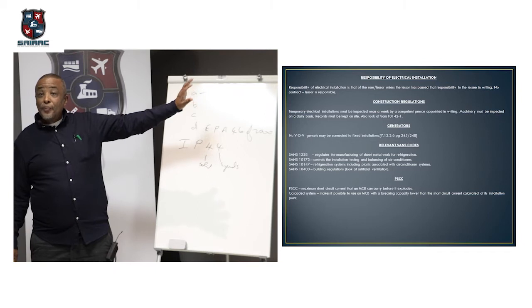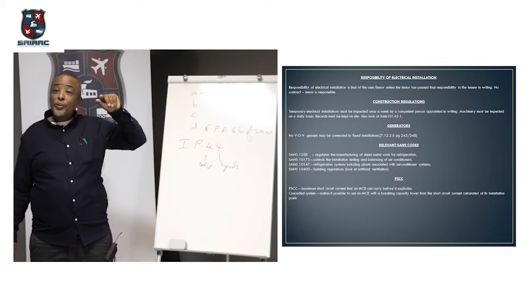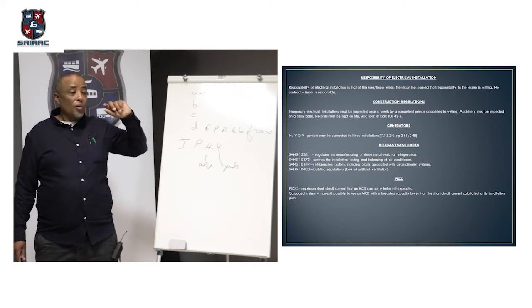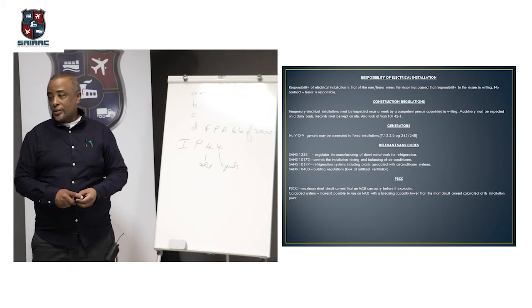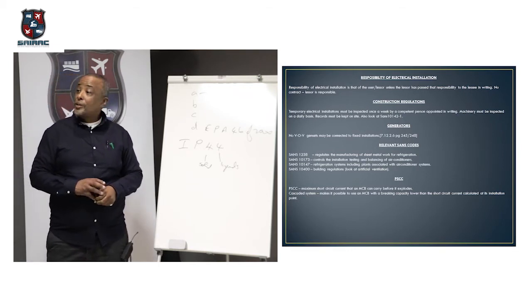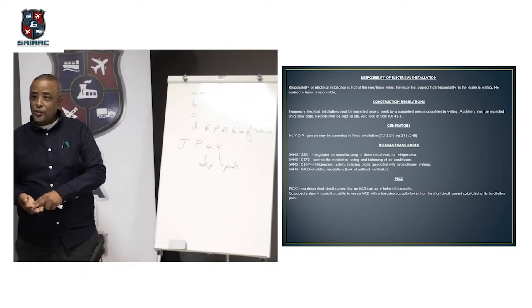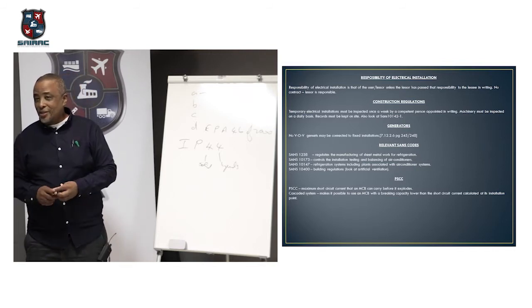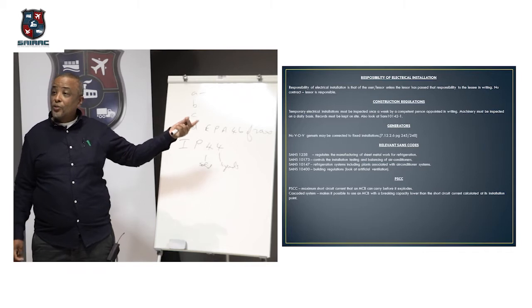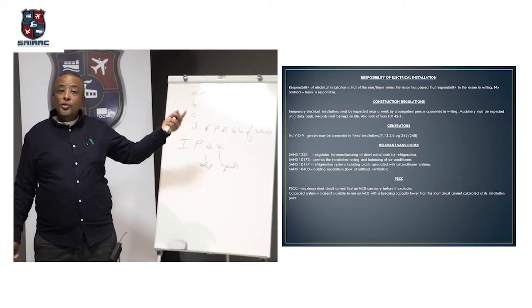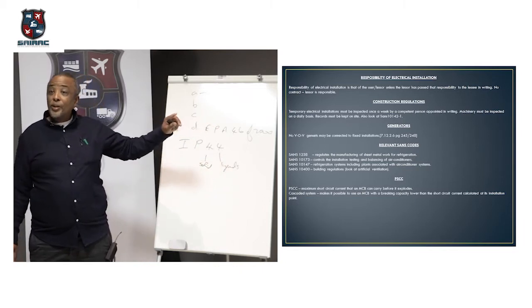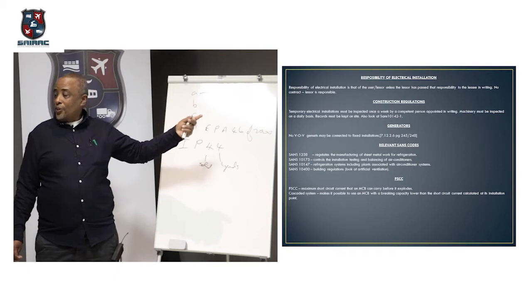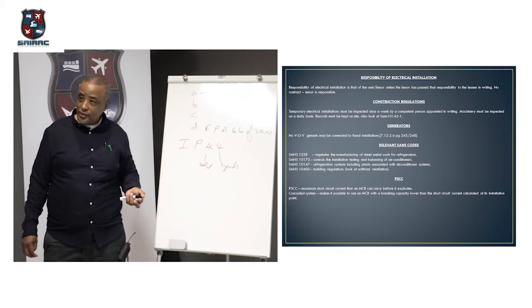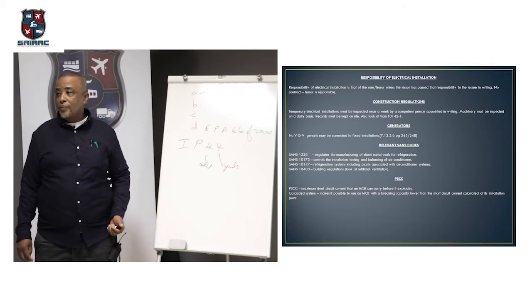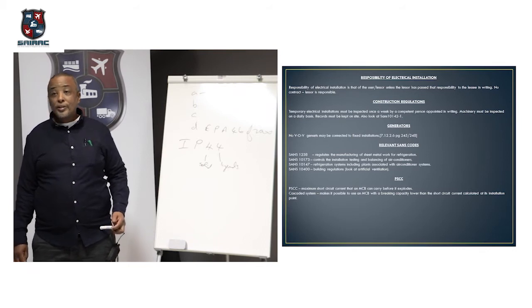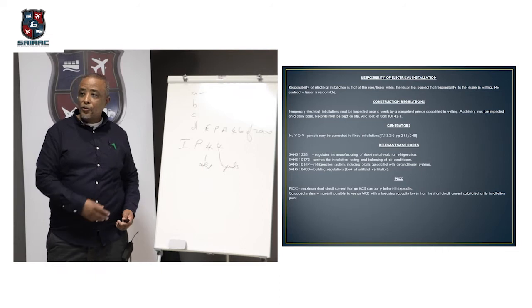All electrical installations, temporary installations, must be inspected once a week by a competent person appointed in writing. All equipment that goes into those socket outlets must also be inspected, but on a daily basis. So every day you've got to check the guy's drilling machine, check the cable's not frayed, the plug top is not broken. Unfortunately, it's in the book. People will say, and it's in the act, so you have to do it. Okay. So for all temporary electrical installations you must exercise general control over it, and that control must be by a competent person, and that person must be appointed in writing. All electrical equipment that gets plugged into the system must be inspected on a daily basis, until the construction site is over.